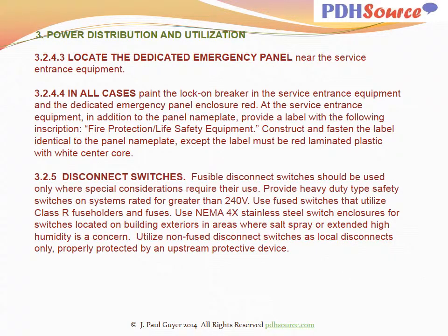Locate the dedicated emergency panel near the service entrance equipment. In all cases, paint the lock-on breaker in the service entrance equipment and the dedicated emergency panel enclosure red. At the service entrance equipment, in addition to the panel nameplate, provide a label with the following inscription: Fire Protection Life Safety Equipment. Construct and fasten the label identical to the panel nameplate, except the label must be red laminated plastic with white center core.